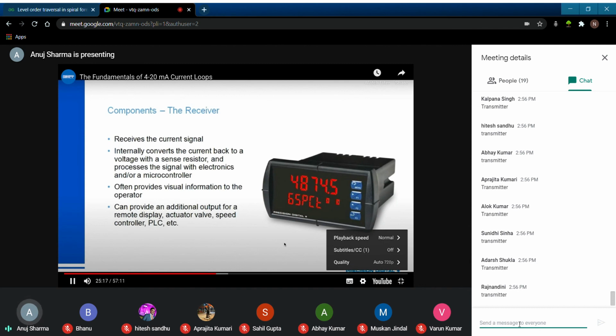So in a case where you have a meter like this, you don't need a separate power supply because it's built into one of your receivers. Similarly, there are transmitters that get powered by some external supply that's not part of the 4 to 20 loop, and they use that to provide power for running your loop.